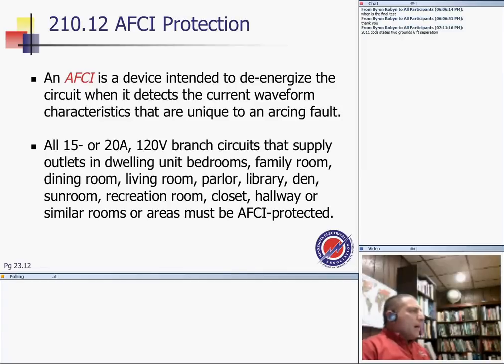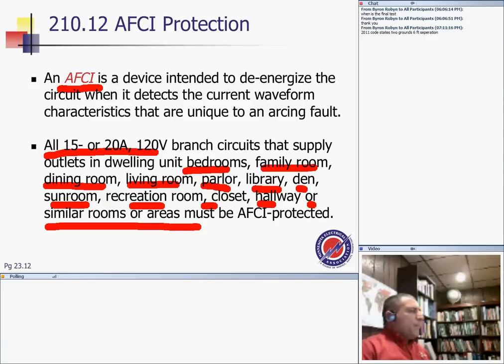Arc fault circuit interrupters, and I'm running through this quick because I'm looking at the clock here. Arc fault circuit interrupters are in dwellings only, so don't think about them in any other locations. They are needed on 15 and 20 amp branch circuits in the following locations: bedrooms, family rooms, dining rooms, living rooms, parlors, libraries, dens, sunrooms, and all the hallways. Basically, any place where you do not need a GFCI. You know, guys, how these work. They look at the signature of an arc, line or series, and if they witness the arc, off it goes.